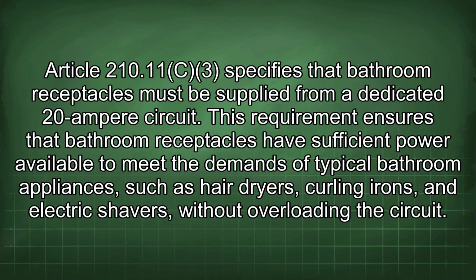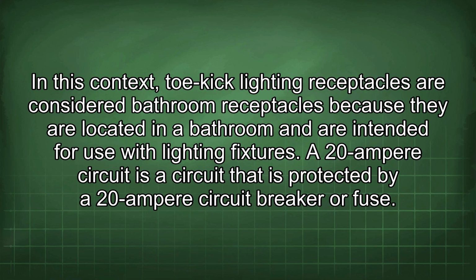Article 210.11(C)(3) specifies that bathroom receptacles must be supplied from a dedicated 20 ampere circuit. This requirement ensures that bathroom receptacles have sufficient power available to meet the demands of typical bathroom appliances such as hair dryers, curling irons, and electric shavers, without overloading the circuit. In this context, toe kick lighting receptacles are considered bathroom receptacles because they are located in a bathroom and are intended for use with lighting fixtures.